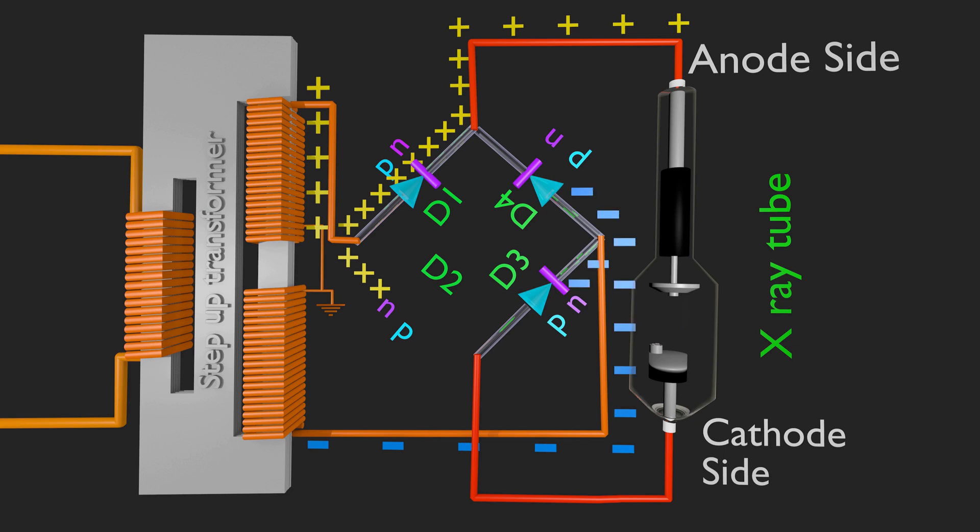Diode 3 is forward biased as N side of D3 is connected to negative polarity. D4 is reverse biased as p side of it is connected to negative polarity. As D4 is in reverse biased condition, it cannot conduct. Cathode side of X-ray tube will get negative polarity through D3.